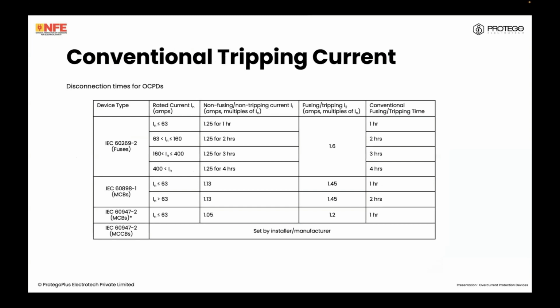Right now, when it comes to the conventional tripping current, like I said, these are talking about overload situations. We all know that if we've got an MCB that's say rated for 16 amps or an MCCB for 16 amps, the moment the load becomes 16.1 amps, it's not going to immediately trip. This is not your instantaneous tripping we're talking about. This is talking about a slow tripping. This is under overload conditions.